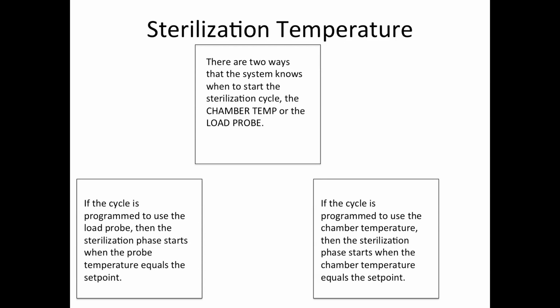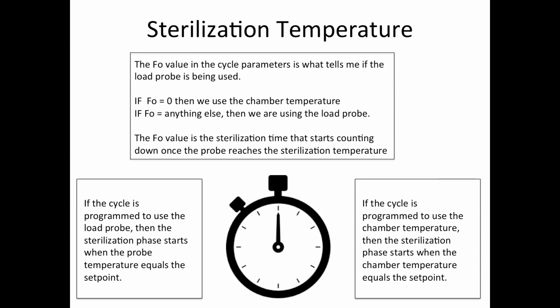of the sterilization chamber. The temperature of your load may not be the same. There may be temperature variations within the chamber. The chamber temperature is an average of the chamber, and when the average temperature of the chamber reaches the sterilization set point, then the sterilization cycle begins. So there's two ways to measure the temperature of the material you're sterilizing. So how do I know which one I'm using?